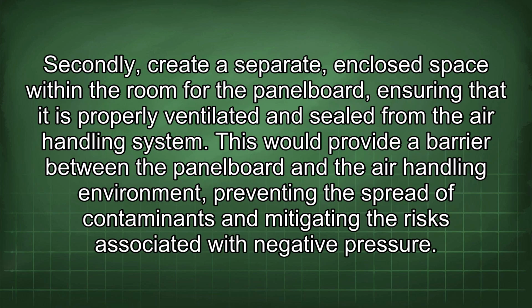Secondly, create a separate, enclosed space within the room for the panelboard, ensuring that it is properly ventilated and sealed from the air handling system. This would provide a barrier between the panelboard and the air handling environment, preventing the spread of contaminants and mitigating the risks associated with negative pressure.